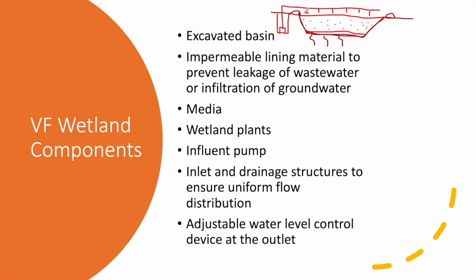At the bottom of these pipes we have plates called splashing plates. They serve two roles: first, to distribute the wastewater equally and uniformly; second, and most importantly, to oxygenate the wastewater. When water percolates onto a plate, air bubbles are created, meaning the water is being oxygenated and aerobic conditions are established, which are very important for the treatment process. We will see the importance of this oxygenation in more detail later.